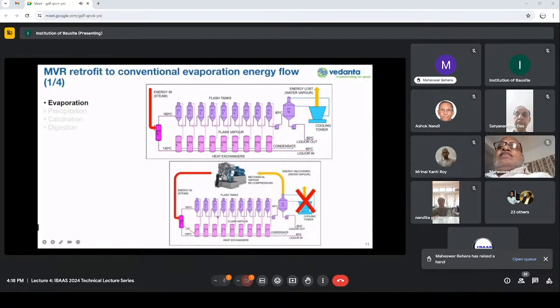Another key factor in this energy flow is the hot condensate from heater 10. If you see, this is heater 10, and the hot condensate is coming from it. Presently, the hot condensate goes to the boilers where the energy is recovered. However, with MVR, the boilers are not used. Instead, the hot condensate goes to HTR9 just next to it, where it provides energy to the liquor being heated, and it continues through the heater train to HTR1 to provide energy to the liquor as it cools. The condensate heat recovery in this and the digestion process in the refinery reduces the overall refinery steam consumption by approximately 5%.